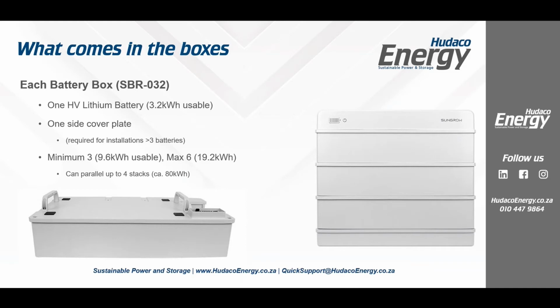And then you simply put your base down, stack battery number 1, battery number 2, battery number 3 in place. You slide your switchgear into the side. I think I've got a better view of that in just a moment. You connect your 4 cables, being your positive, your negative, your earth, and your comms cable, and then you pop your BMS on the top. It's a 10-minute process at max. It's so fast, so quick, so simple.